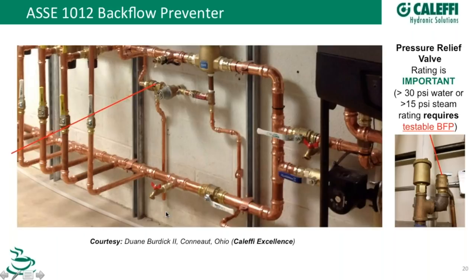Caleffi includes the air gap adapter with their 574; with other brands you have to buy it separately — it's called a Tundish in Europe. Shown here is a nice illustration of the green tagging for safe water and the upper right corner showing protected water continuing past the backflow preventer to a pressure reducing valve for common plumbing fixture use, while high pressure continues to a laboratory. The identifying triangle is pretty universal, and you can see the annual test report hanging there at the assembly.